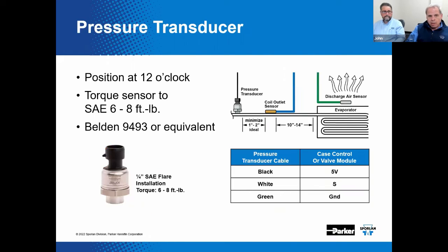Makes sense. Now, here we discuss the pressure transducer. We also need to manage things like superheat. You need both temperature input and pressure. And of course, you're interested in what's going on with pressure for a number of things. Here we have detailed one of our newer pressure transducers that we make available. And we talk about mounting it at the 12 o'clock position on a refrigerant line and torquing the sensor to 6 to 8 foot-pounds. And there again, we're specifying a Belden code, if you will. Now, and then we got different case control or valve specifications here in this table.